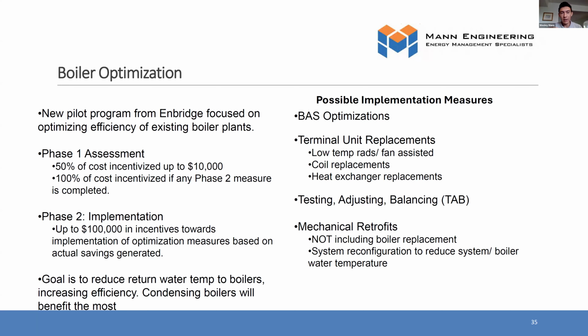Whereas if you could just adjust the balancing in the building so that the building's heated more consistently, then all of a sudden you can bring your boiler temperature, your outdoor temperature curve down, because you're no longer having to worry about maintaining that one riser that doesn't get enough heat anyways. Well, meanwhile, you're cooking the rest of the building. So a lot can be achieved just through rebalancing of the systems.